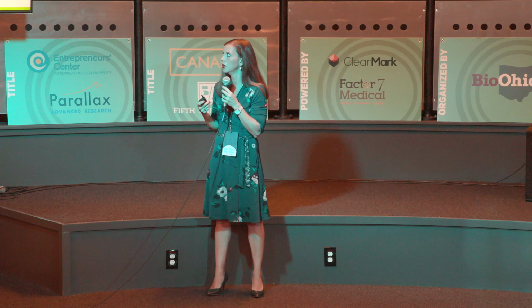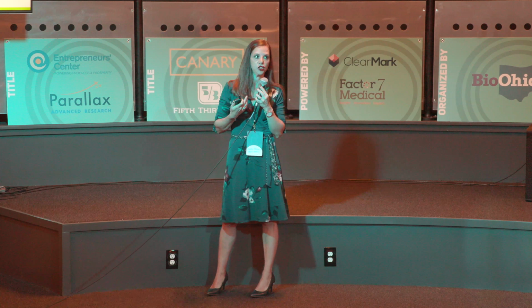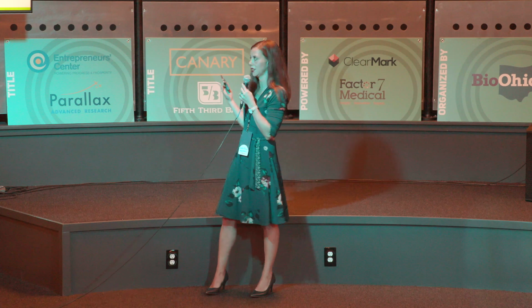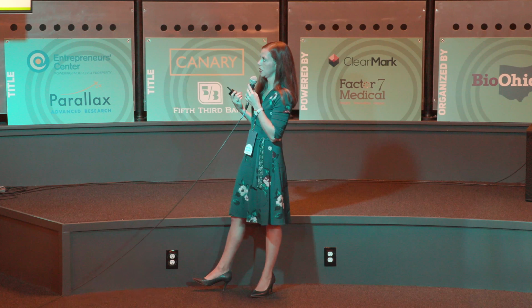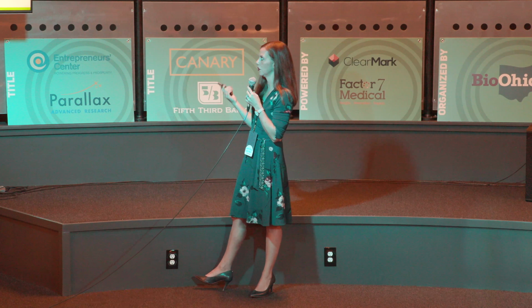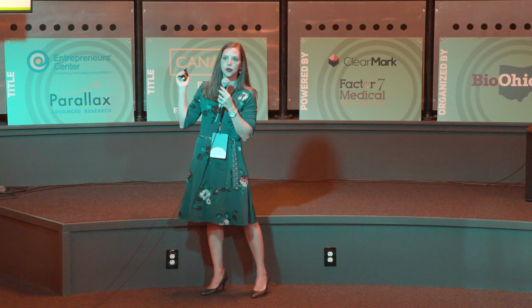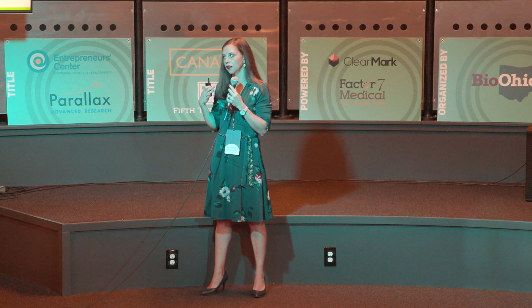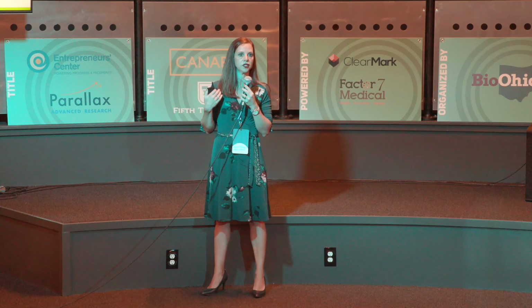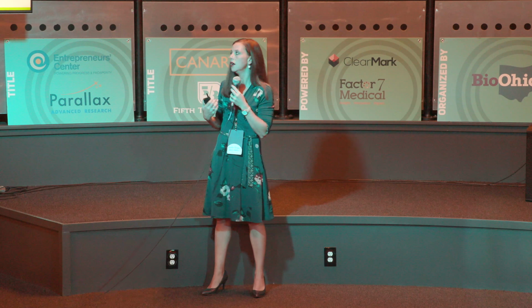The next biggest point is the verification and validation. So again, as you're stepping through the development life cycle, there's the engineering analysis and the finalization of the specifications that this product is actually going to function for long-term use in whatever capacity it needs to. So I've listed here, you have bench and mechanical testing. This device here is an Instron machine going through mechanical testing. So, in the spine, for instance, it has to withstand 5 million cycles for so many loads, the loading of the spine of a person.